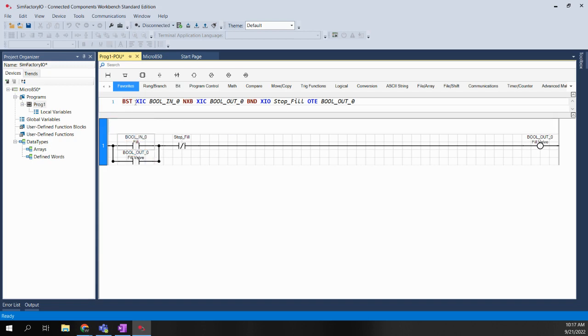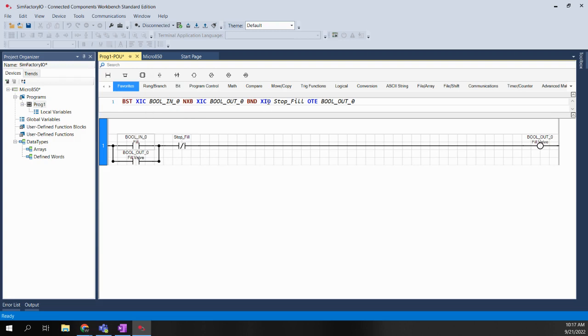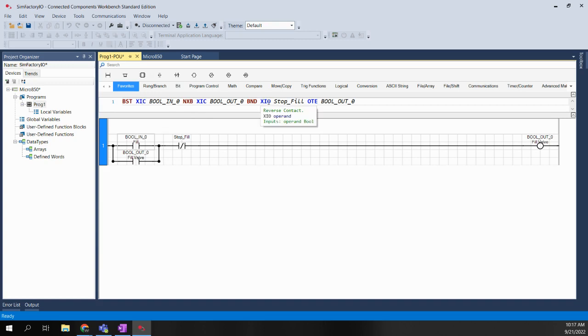Going back to some older Allen-Bradley PLC programming days, there was the ability to write out Boolean instructions in a shorthand method. In those days, they used XIC and XIO terminology — XIC stands for 'examine when closed' and XIO stands for 'examine when open.' Basically, XIC is the shorthand for a normally open contact and XIO is the shorthand for a normally closed contact.